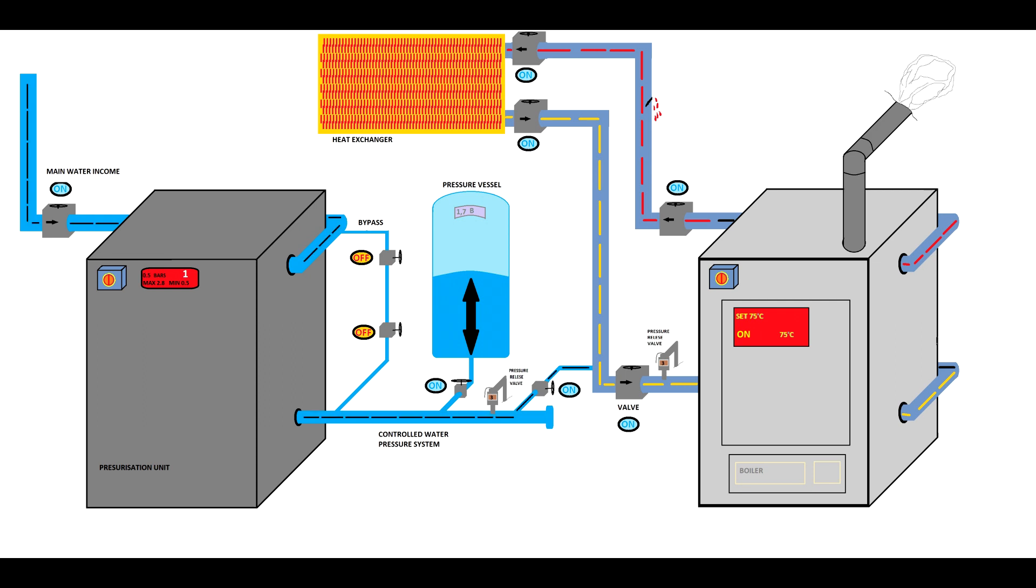If you have a leak, the pressurization unit starts counting. Some very old pressurization units will push water into the system constantly and flood the premises. Modern units will push water from one to one hundred times—it's up to you. I usually allow them to push water only ten times, and after ten times they will stop.